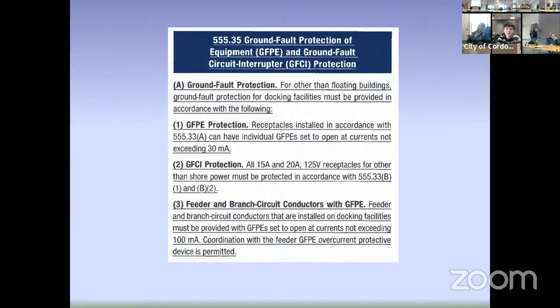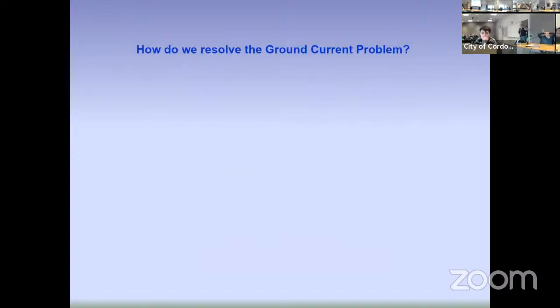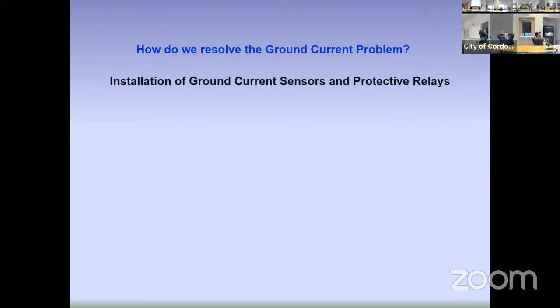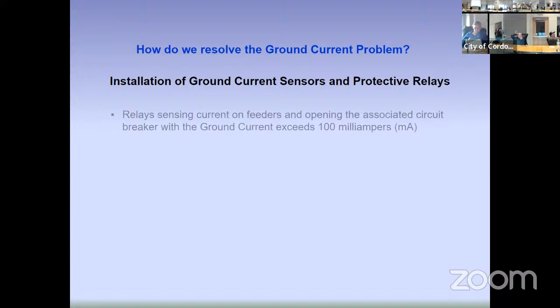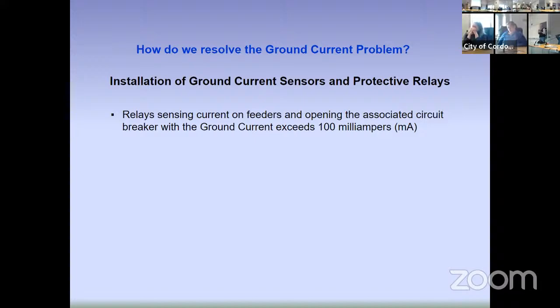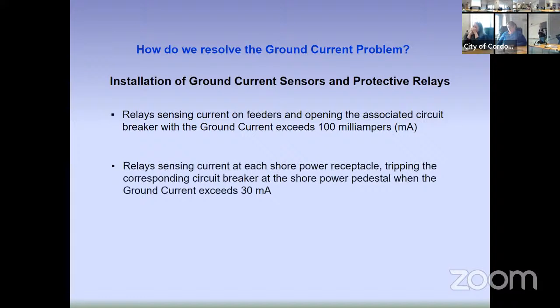Let's go to the next one. This is, I pulled this out of the code, and it talks about each of these specifically. Let's go to the next one. So how do we resolve it? Let's hit the next. So we have the installation of current sensors and protective relays. Next. And the relays will be sensing the current on the feeders and opening the circuit breakers on the feeders when it exceeds 100 milliamps. Next. And then each shore power receptacle will trip at 30 milliamps. Solution is to upgrade the boats, ensure that the wiring on the boats is such that we don't have a ground current.